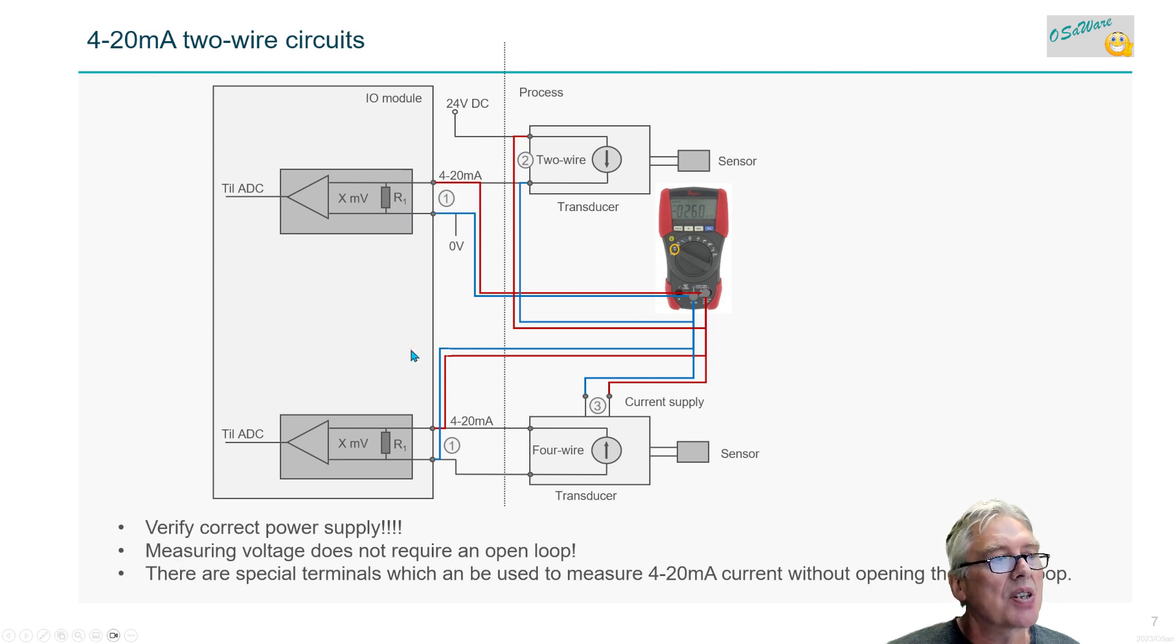You can use the same for a four-wire. First thing you do is measure the power supply. There exist special terminals where you can measure 4-20 milliamps using voltage and you get a reading also 4-20 milliamps, so you can read the signal itself without breaking the circuit, which is kind of nice.